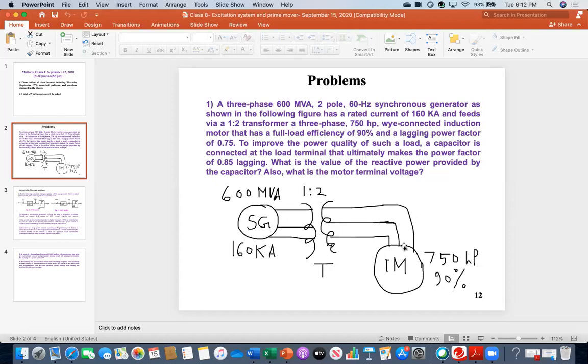And then that motor has a lagging power factor of 0.75. Now, to improve the power quality of such a load, a capacitor is connected at the load terminal, which ultimately makes the power factor 0.85 lagging. Here at this terminal, you connect a capacitor. You all know that a capacitor can raise the power factor. That capacitor made the power factor 0.85.